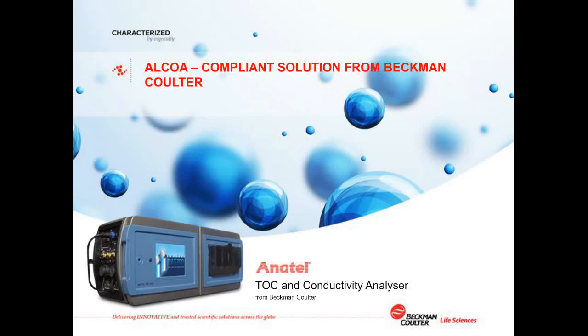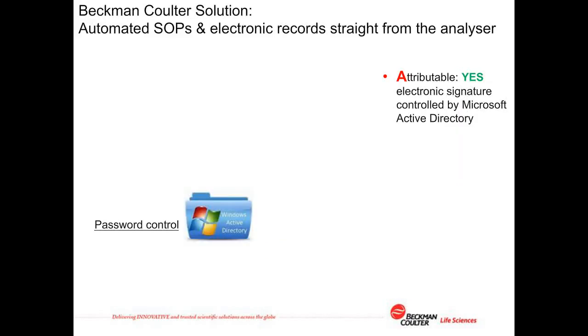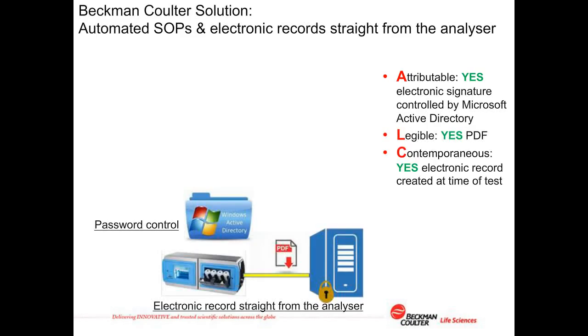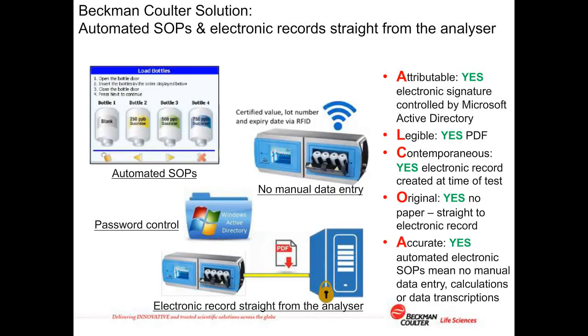So what can be done to provide an ALCOA compliant solution for online monitoring of water for injection systems? Fortunately, an ALCOA compliant solution exists. The Anatel PAT, TOC, and conductivity analyzer from Beckman Coulter automates all the SOPs, eliminating manual data entry and calculations, and creates an electronic record straight from the analyzer. Signatures are attributable and controlled by the site IT team using Microsoft's Active Directory controls.